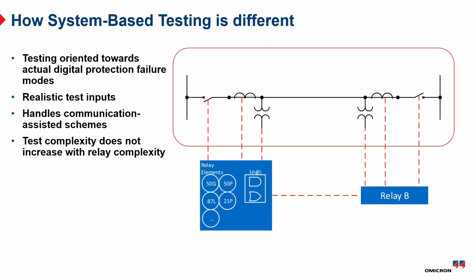This is really much better oriented toward testing how relays actually fail in the field. It handles communication, and test complexity does not increase with relay complexity. As you can imagine, with really simple relays, creating the model of the system is more work. But as we get these more sophisticated devices, at some point the seesaw balances the other way, and it becomes easier to model the system than to try to model all of the nuances in the protective relay's algorithm.